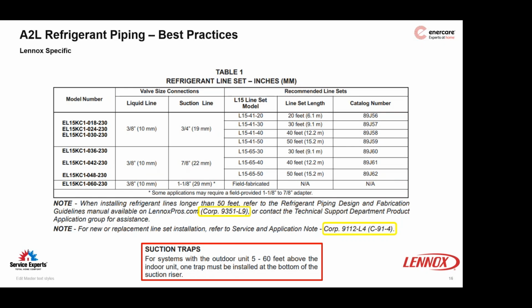Again, if you're having trouble sleeping and you're looking for something to read at night, the refrigerant piping design guideline is great reading material for that. But if you just have some general questions, they have some pretty good answers on how to pipe and how to apply suction traps and riser traps if you need them, and anything beyond 50 feet within the piping guidelines.